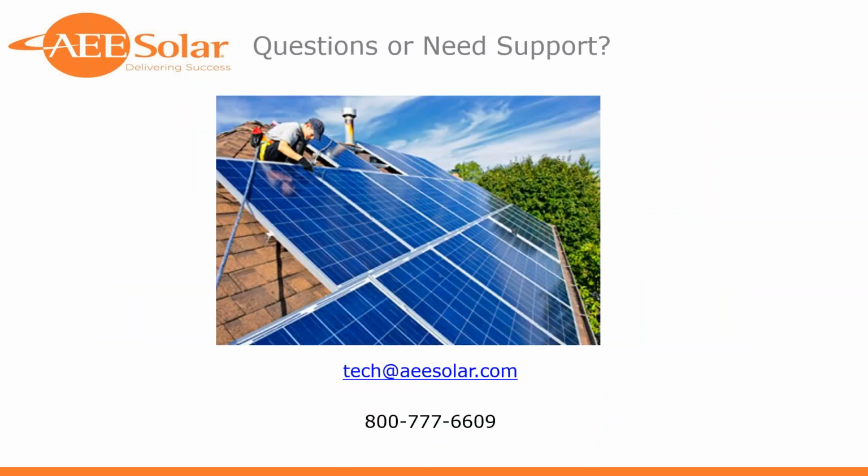One thing that I did not touch upon, and it's occurring to me as we end here, is if you're looking at one of these solutions and you're trying to have the best of both worlds in terms of self-consumption with backup, you've got to think about, if this is a battery that's being cycled for self-consumption, how much reserve do you program in for backup? I've seen typical applications using SolarEdge and LG Chem where 20% is reserved for backup overnight. So you fill the battery up during the day, you discharge it during the afternoon and evening, and you're leaving 20% of that usable capacity for backup. If there's an outage overnight, are your loads backed up until the next morning when you can recharge from PV? That's real easy to do on some systems. It's a little harder to think about in the design stage. And are you sizing your battery properly for cycling and backup? So while we've got the benefit stacking there, it could lead to a little more storage that you're going to need.